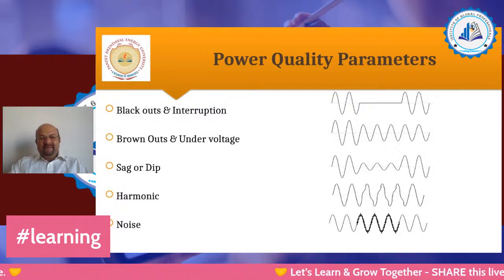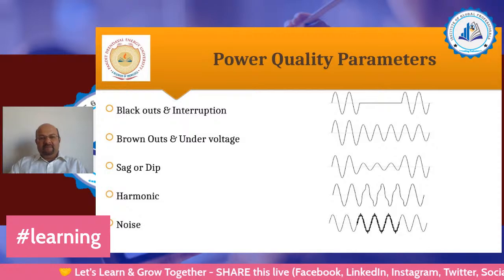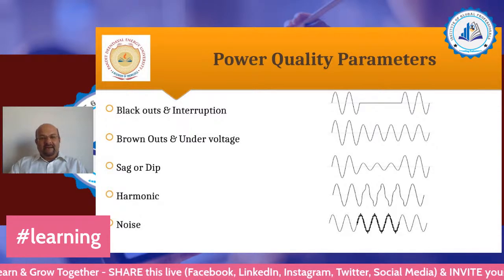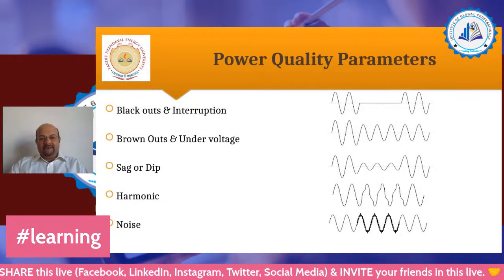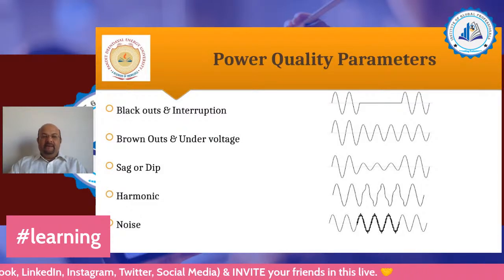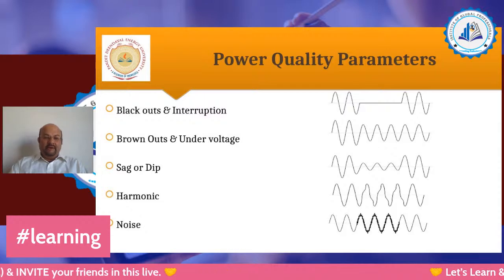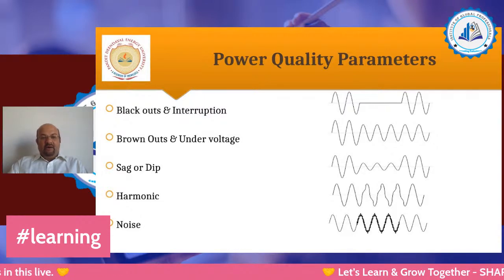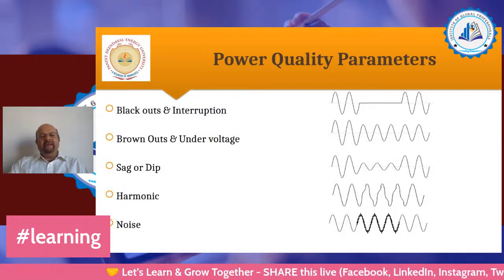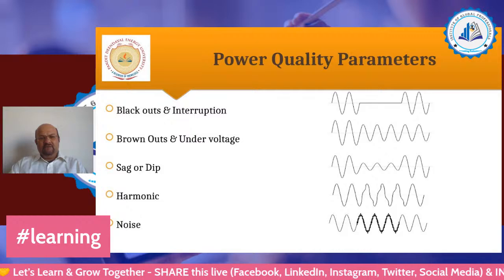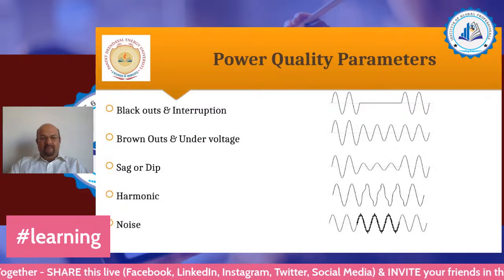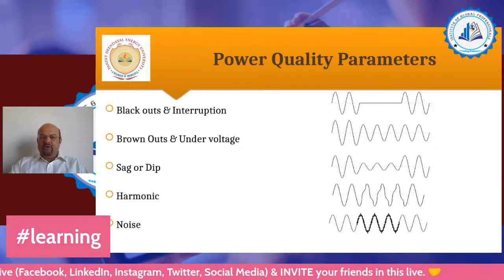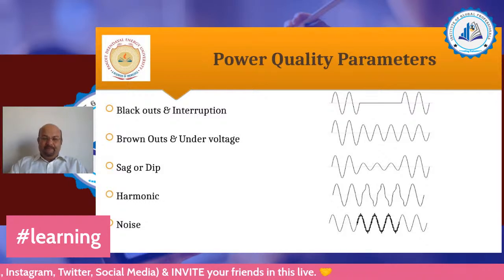Brownout means that the amplitude of the waveform, that is the voltage, is normal, and then for this much time the voltages are reduced. That is an RMS reduction, and it is sustained. So this phenomenon or parameter is known as brownout or undervoltage. Now sag or dip is again an RMS reduction, but for a very limited time, a couple of cycles to maybe a couple of seconds only. It is not sustained, so it cannot be called undervoltage.